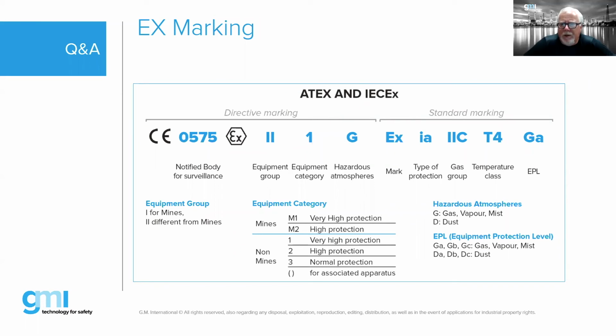Then the standard marking is your EX mark, telling you it's explosion protected. In this case, using intrinsic safety with redundant fault tolerance, actually double fault tolerance, EXIA. And that's the difference between EXIA, IB, and IC: the fault tolerance. The gas group, Roman numeral 2C, means it's good for all gas groups. And then T4, which is the T code, which is based upon a normal ambient of -20 to +40, unless the product has something above that, which I know GMI, we talked about that last time. I think your rating is actually to +70 degrees C.